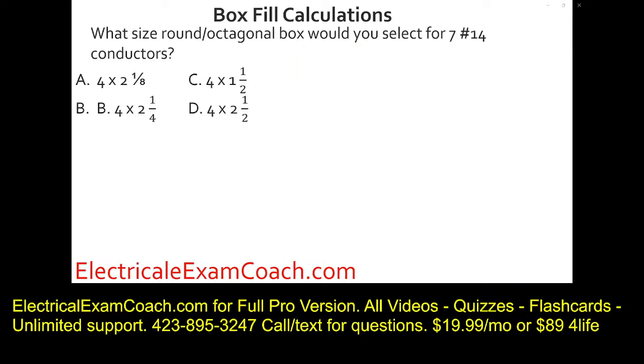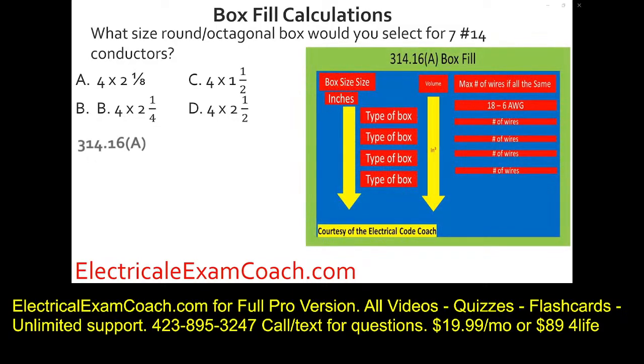What size round octagonal box would you select for 7 14 gauge conductors? We're going to head to Table 314.16a. We're going to start here on the right-hand side and we're going to find our gauge wire. Then we're going to come down and find a box that fits it and be sure when we cross over that we stay in the right category of box, and we're going to select C.